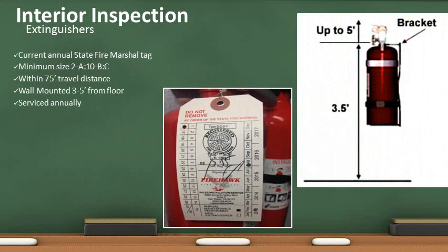All fire extinguishers must be visually inspected monthly and serviced annually. Records of this inspection and service shall be kept on site. The minimum size for extinguishers is 2A 10 BC. As with all other extinguishing equipment, a minimum of 3 feet of unobstructed space is required for access.